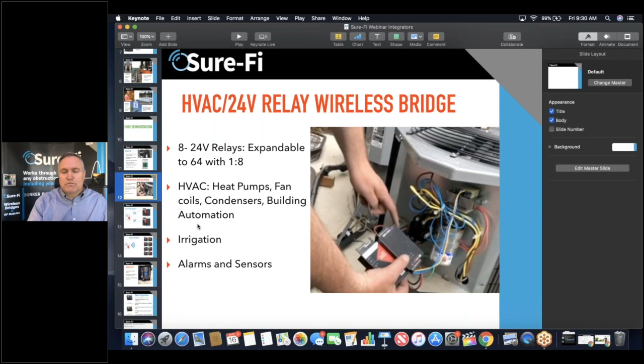So we'll jump right down here to the HVAC. The HVAC is a 24 volt setup, just like most HVAC systems. But what it can also do, which is really nice, is be expandable from one to multiple. It's been used for heat pumps, condensers, building automation. They use it a lot for triggering alarms or resetting alarms, and for sensors and things.